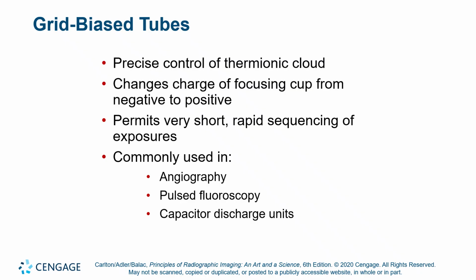So dose the patient in pulses at the same frequency as your detector reads out. If your detector can read out 30 images per second, then give it 30 pulses per second and you're not wasting any X-ray. You're capturing and converting 100% of that X-ray pulse to another image, a brand new image. Okay. We'll talk more about pulsed X-ray when we get to the fluoroscopy and digital fluoroscopy unit this fall. Okay. But you utilize a grid bias tube in order to create that machine gun burst of X-ray.